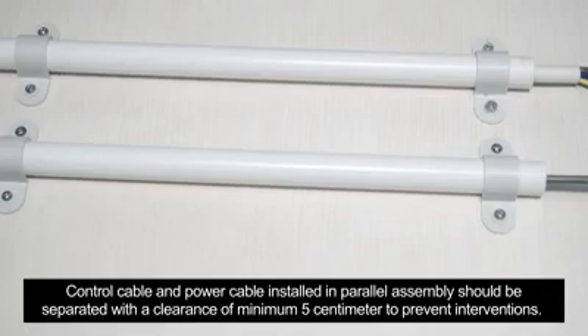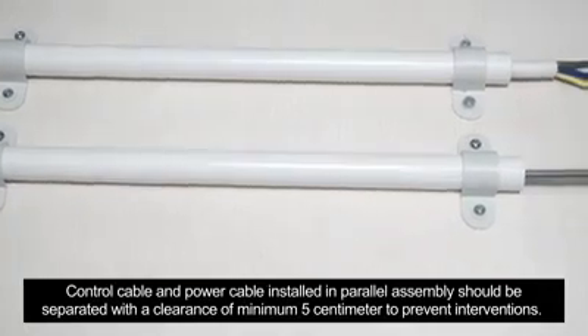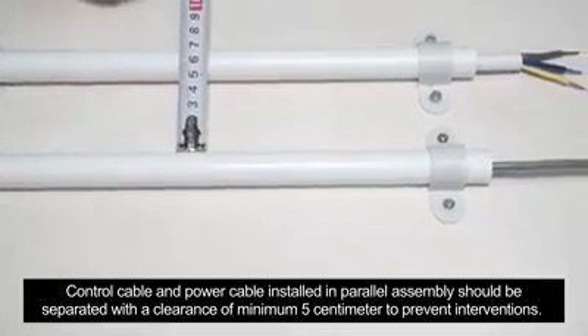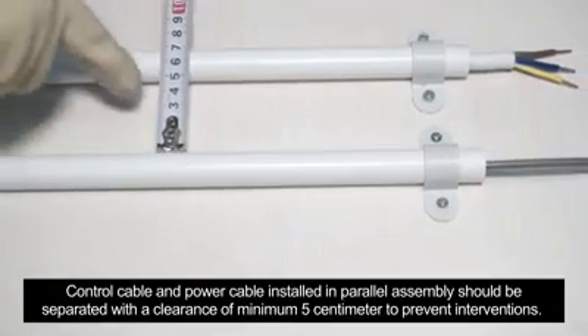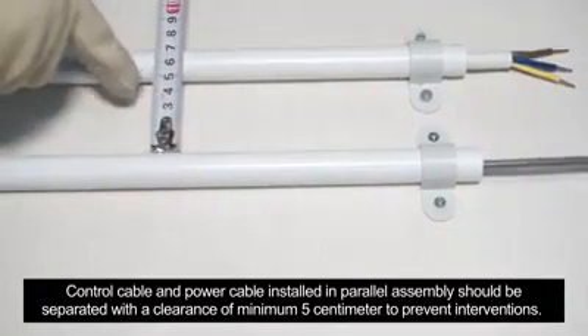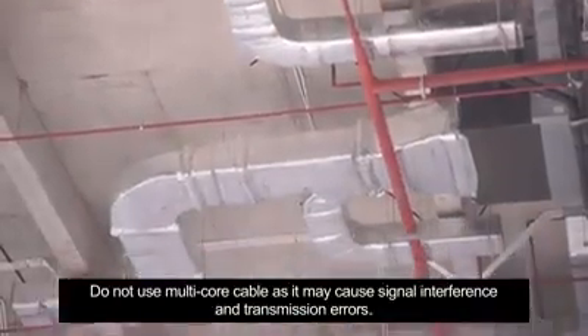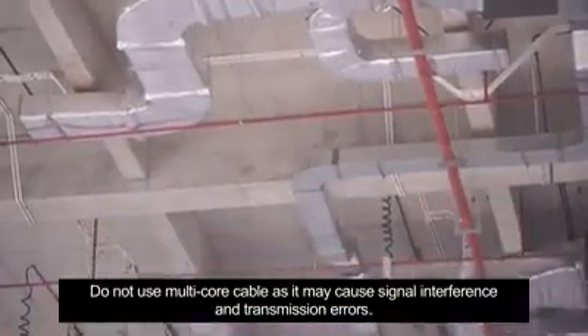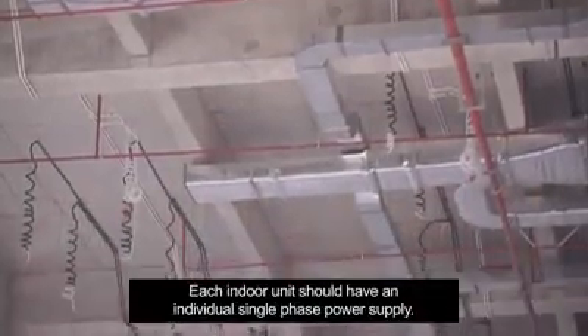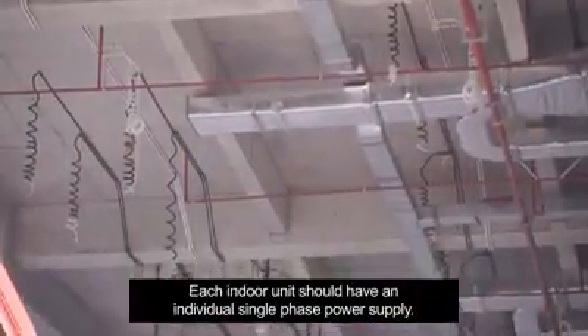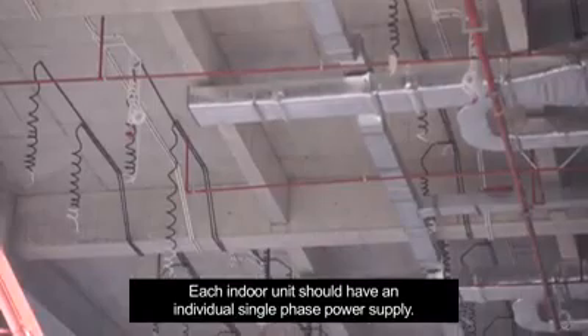Control cable and power cable installed in parallel assembly should be separated with a clearance of minimum 5 cm to prevent interventions. Do not use multi-core cable, as it may cause signal interference and transmission errors. Each indoor unit should have an individual single-phase supply.